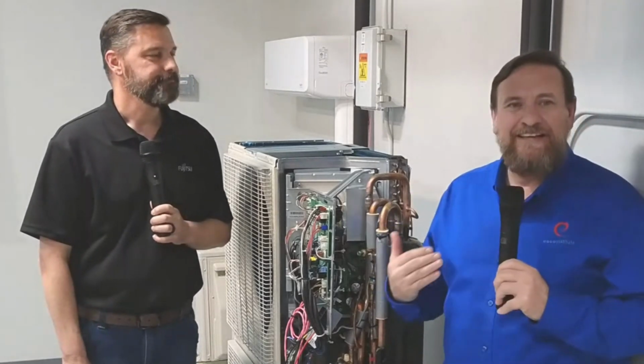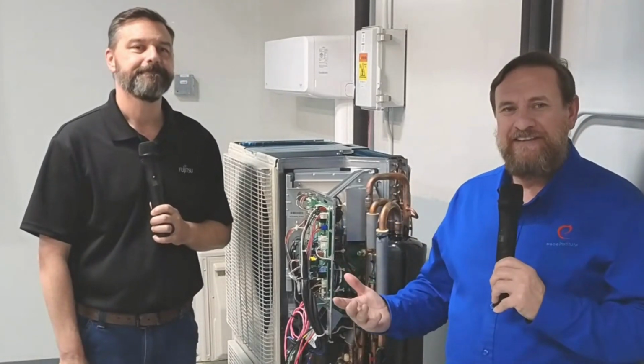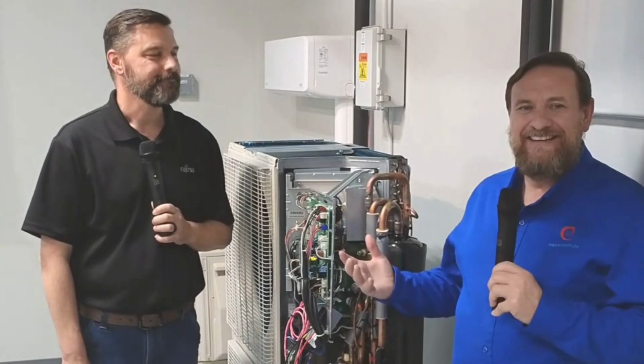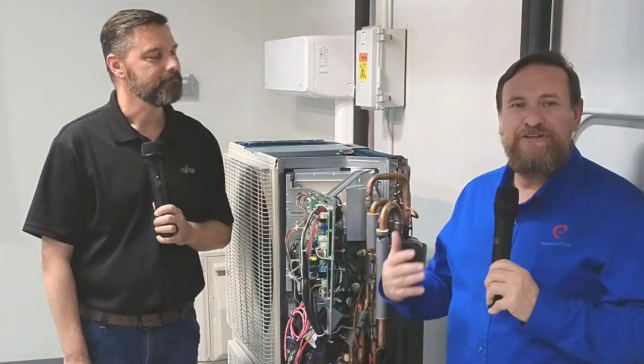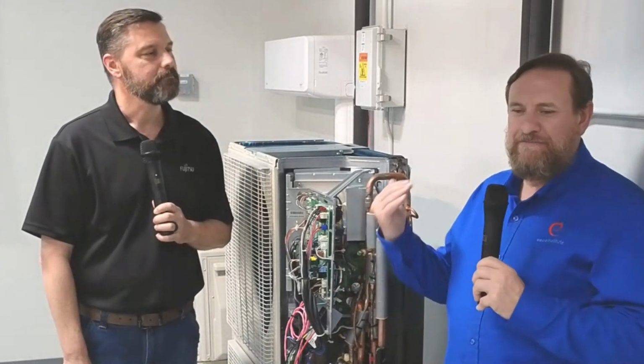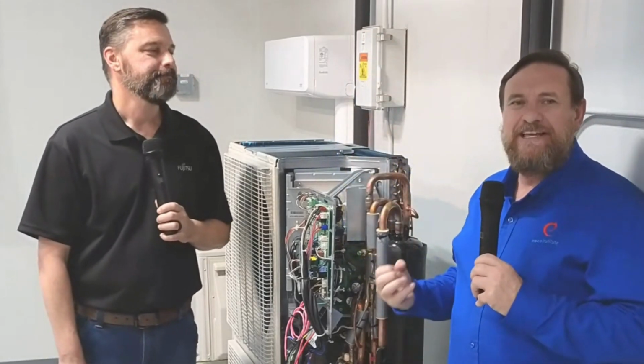It's an amazing difference. We talk about that decay test. I talk about vacuum all the time, and I talk about giving it time to see if that moisture re-evaporates out of that system. But here they're giving it that decay test, waiting for an hour to make sure it doesn't rise above 500. You're always hearing 500 microns, like that's a goal. No, we want to be below that. We want to make sure we don't ever rise above 500. 500 is the limit, not the goal. That's like the highest level. Because if we get that moisture out, we're good.